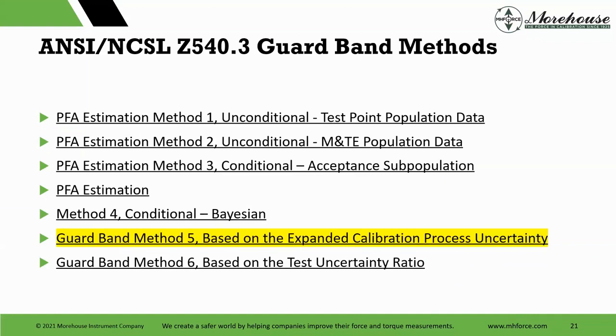Method 1, estimation, unconditional PFA. You just need a lot of data. To simplify it and not get too into these methods, we'll look at method 5, which is based on the expanded calibration process uncertainty, and method 6, which is based on TUR or test uncertainty ratios.